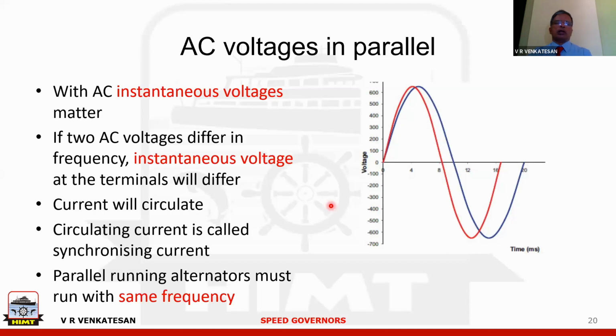So one of the very important rules with parallel running alternators is that they must run with the same frequency all the time. They cannot run at two different frequencies. And their terminal voltage waveforms must be always matching. They will exactly match. Anytime there is a difference, it will correct internally. Electrically, it will correct. So when you keep this principle in mind, the next point will be easy to understand.